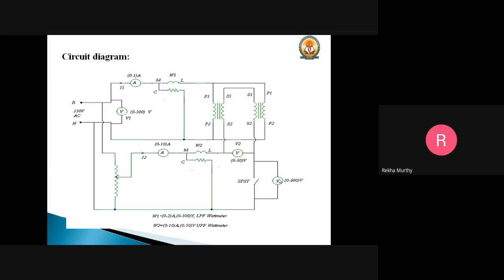If the voltmeter indicates zero reading, then the SPST switch is closed and we can conduct the experiment. If the voltmeter indicates twice the secondary voltage, then the secondary terminals of any one of the transformers will be interchanged to make the voltmeter read zero. Then only the SPST switch is closed. We must ensure this voltmeter reads zero when the SPST switch is open. If it reads twice the value, we must switch off the supply and interchange the connections of the secondary windings.